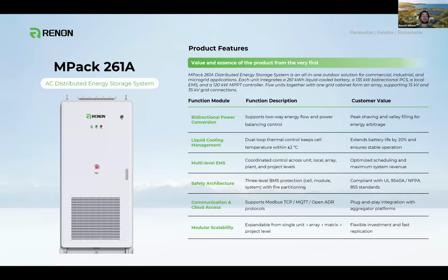The major advantage this brings is that rather than it being a 480 Delta native configuration, it comes out 480Y. Having that neutral line removes the need for the isolation transformer that has been part of all system design for the 233. That upgrade is a massive improvement to the quality of the product and helps prevent the need for additional isolation transformers, and it provides load balancing from the get-go right out of the PCS.